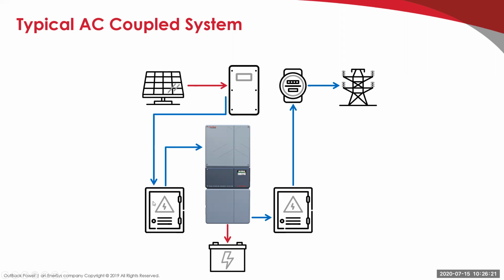Now, the other thing that we did add is we have a backup load panel here, our critical loads panel. So we moved some of the circuits off the main panel over to the backup load panel. But other than that, we're just in series. This is what I call copper wire mode when we're grid connected. We're just like a piece of copper wire. We're no different than it was before. The grid tie inverter is still powering the loads. We've moved some of them over here, but it's just basically operating like it was before. We put our inverter in series, okay? And then of course we have the batteries.